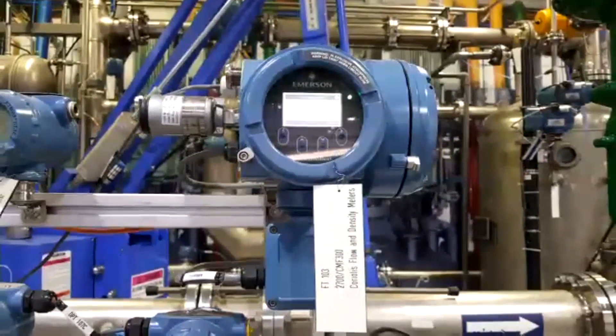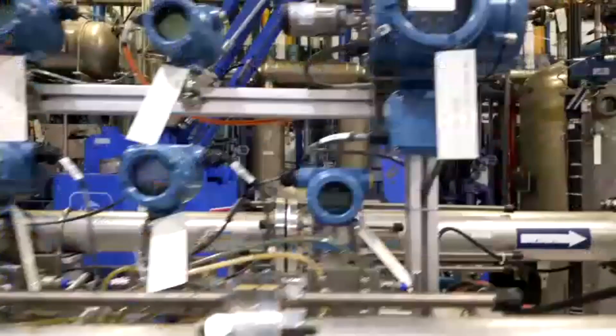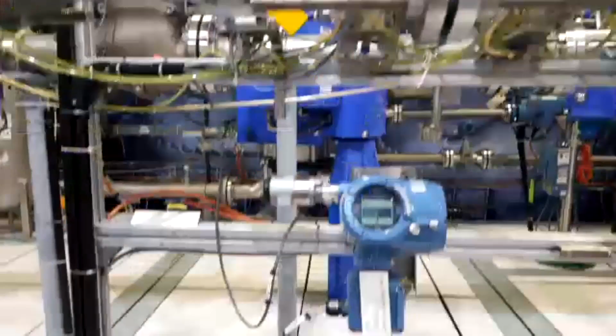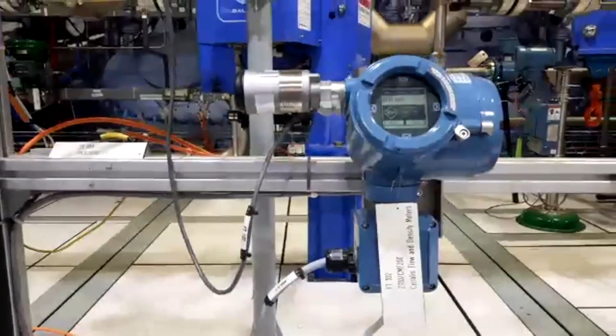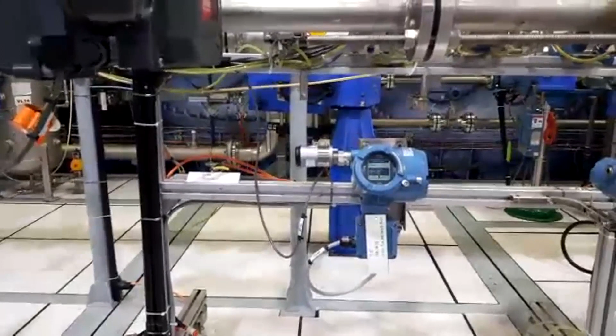So what I wanted to show you today is, for sub-metering, which is so important for energy management, you can use Coriolis flow meters. So that is a 4-wire transmitter, and down here we have a 2-wire Coriolis flow transmitter. As you can see here, it's fitted with the wireless HART adapter. So even though this is a 2-wire device, with loop power to power the sensor or the measurement tube, we still have wireless data transmission through the wireless HART adapter. Remember, wireless HART is really one of the few protocols out there for wireless sensors that support HART adapters.